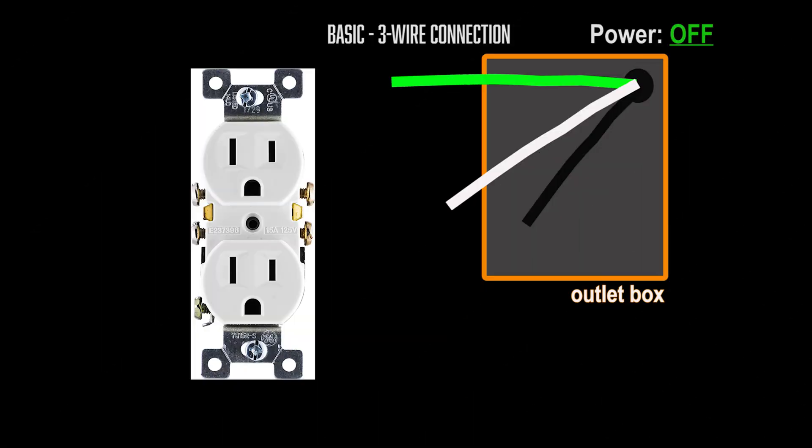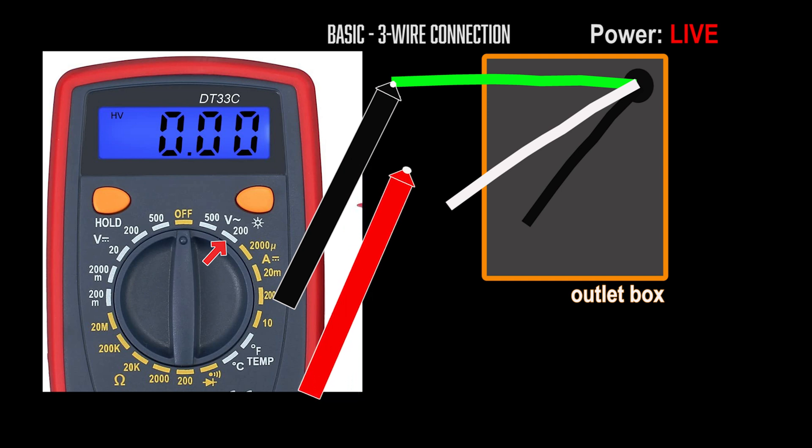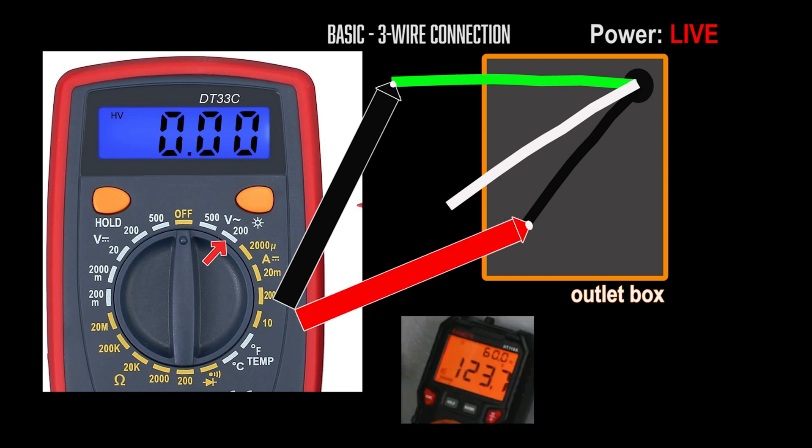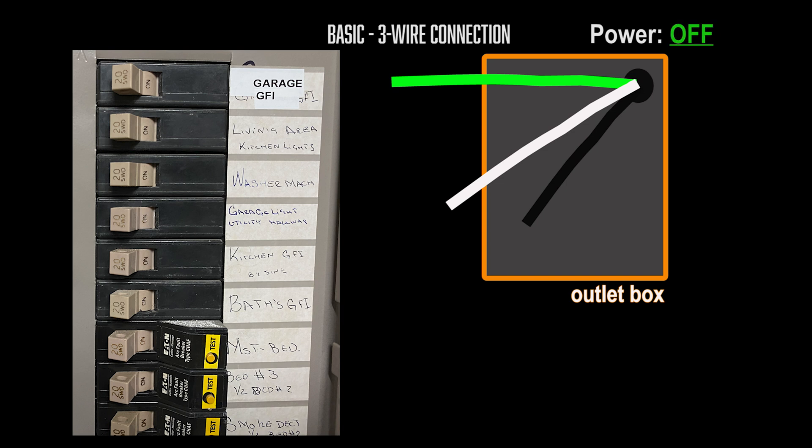To correctly identify the wires, you want to disconnect all three of them and spider them out so they do not touch each other. After that you can go back to the circuit breaker and turn it back on. Now you were expecting the hot wire to have the current, while the neutral one will be dead since it's not connected into the power loop. With the multimeter setting on AC, place the black lead on the ground wire and the red lead on one of the wires in question. If there is no reading, move the red lead to the other wire. Whichever one shows the current is the hot wire. Usually it's the black wire. The wire without the readings is the neutral.